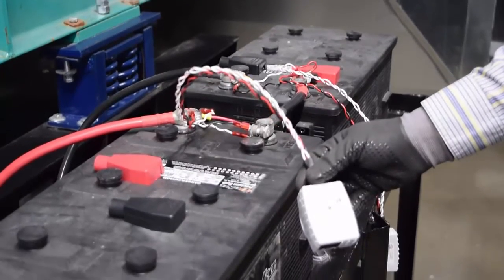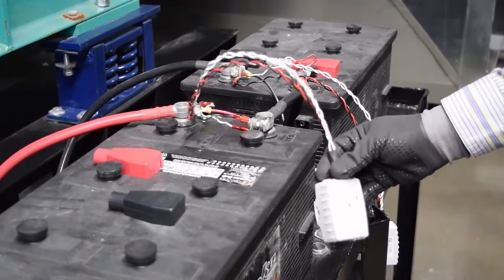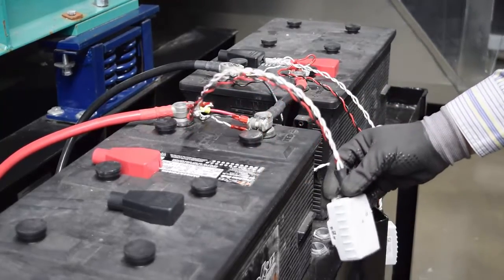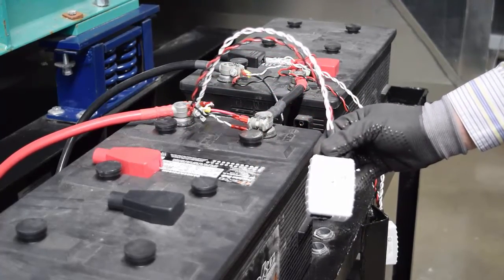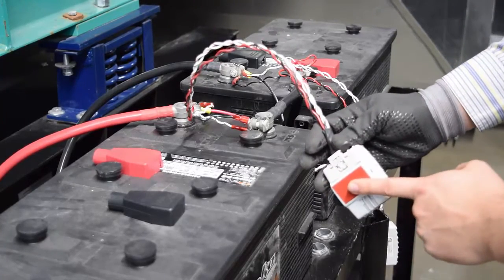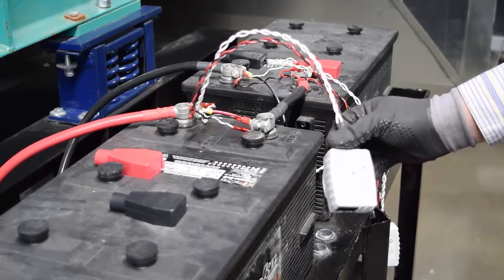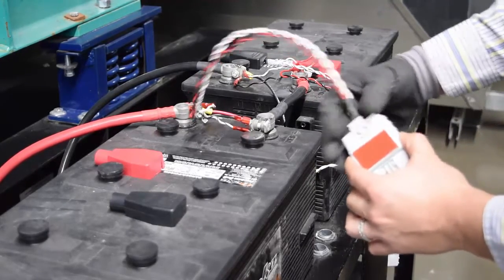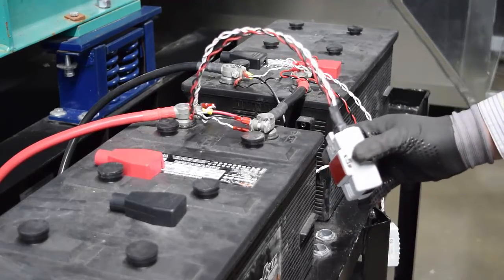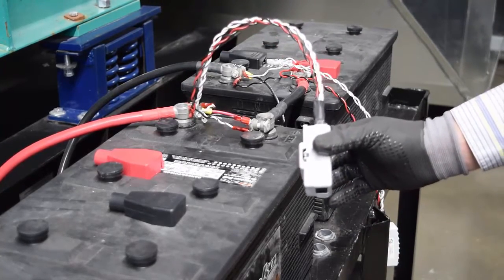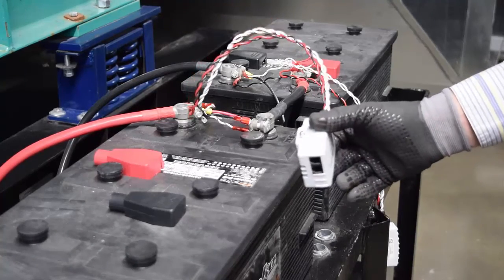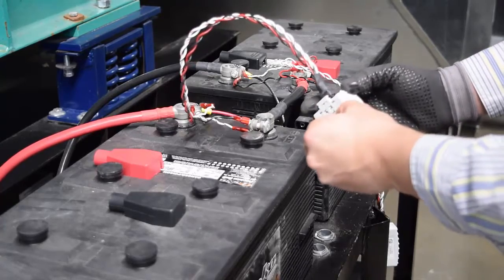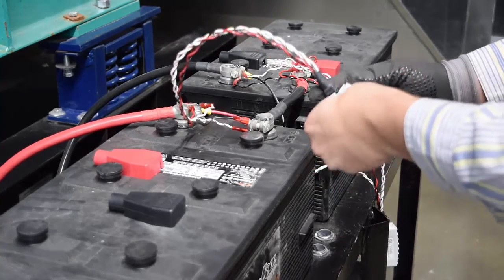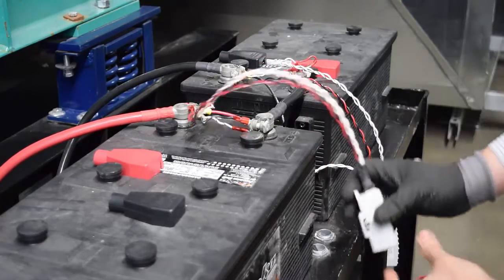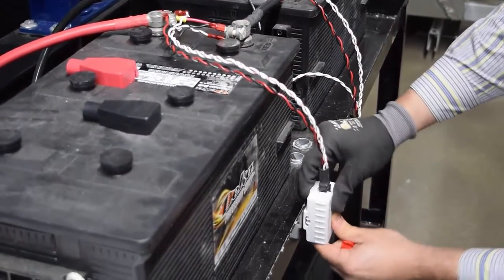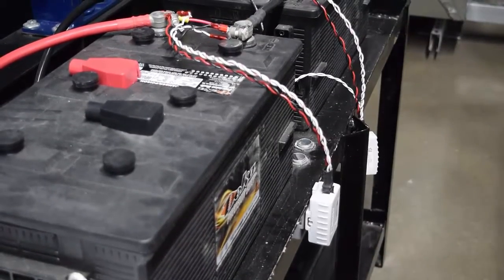Now we got to mount the VTZ3 modules. And we want to mount them in a way that does not put tension on the connector or the cable harness. There are 3 options. You can mount it to the battery rack using the adhesive mount, which is what we're going to do today. We could mount to a DIN rail using an insulated screwdriver to pull this latch onto a DIN rail. Or you can mount the VTZ3 to the battery bus bar using a zip tie. So now let's just peel and stick. Very simple. And no tension, good to go.